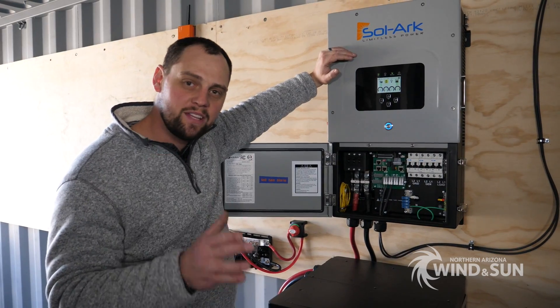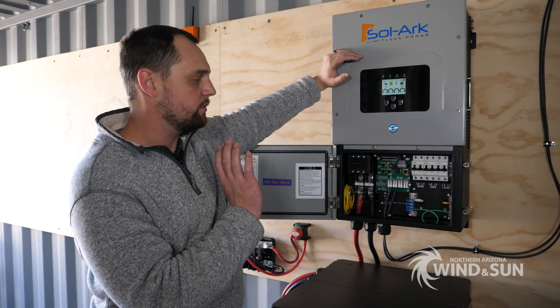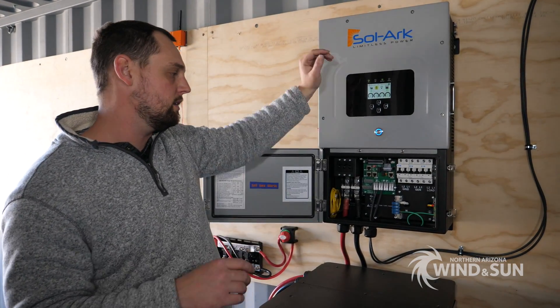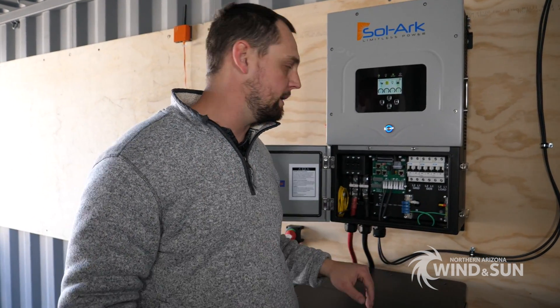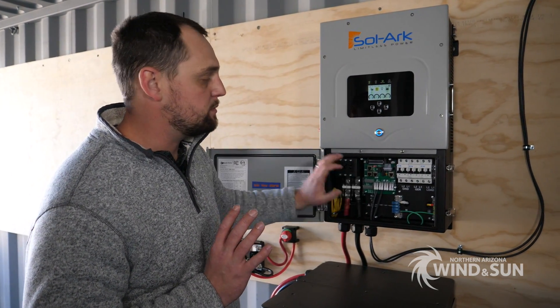In a grid-down situation, the Sol-Ark is an 8,000-watt inverter — it can feed essentially 8,000 watts to the loads. It can handle surges of up to 16 kVA for about 10 seconds and 20 kVA for very intermittent surges.